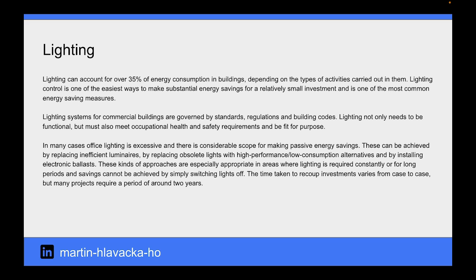Lighting not only needs to be functional, but must also meet occupational health and safety requirements and be fit for purpose. In many cases, office lighting is excessive and there is considerable scope for making passive energy savings. This can be achieved by replacing inefficient luminaires, by replacing obsolete lights with high performance, low consumption alternatives, and by installing electronic ballasts. These kinds of approaches are especially appropriate in areas where lighting is required constantly or for long periods and savings cannot be achieved by simply switching lights off. The time taken to recoup investments varies from case to case, but many projects require around 2 years.